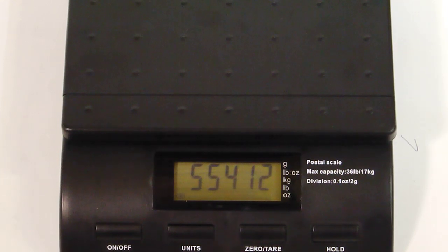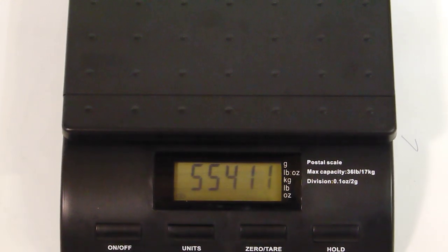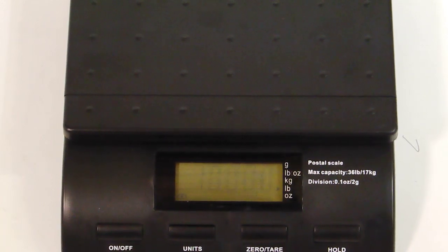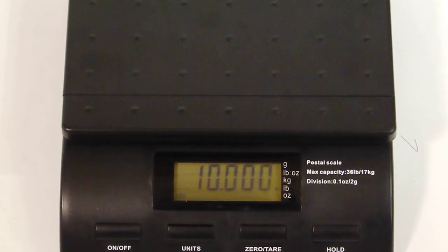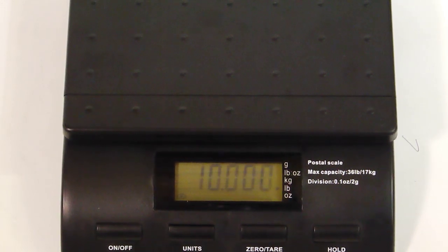Next, press the unit key to capture the zero point. No weight on the scale platter yet. The display will show a series of lines and then the calibration weight.